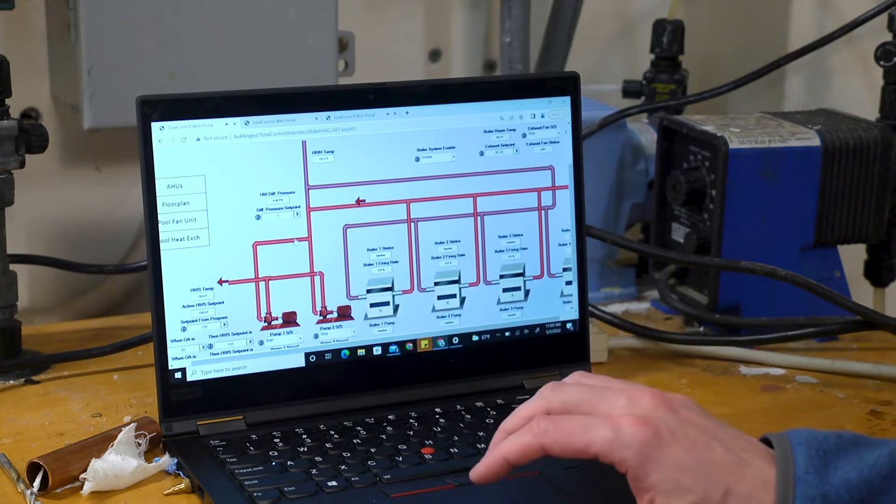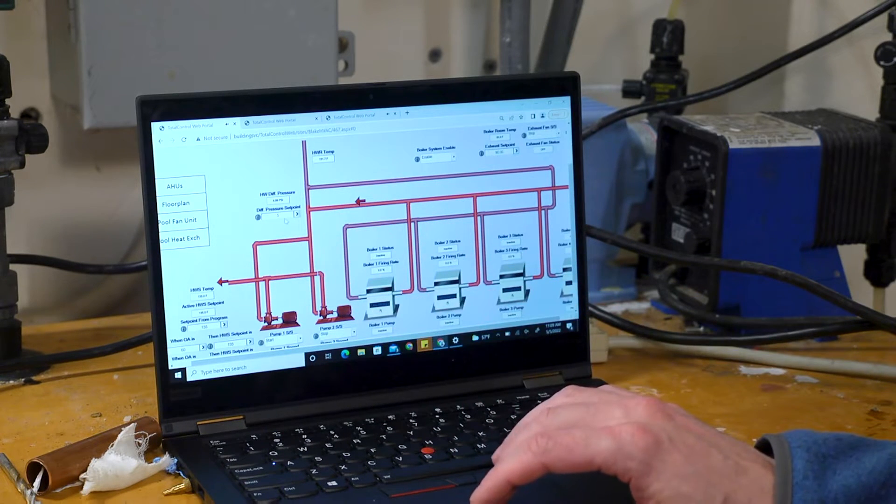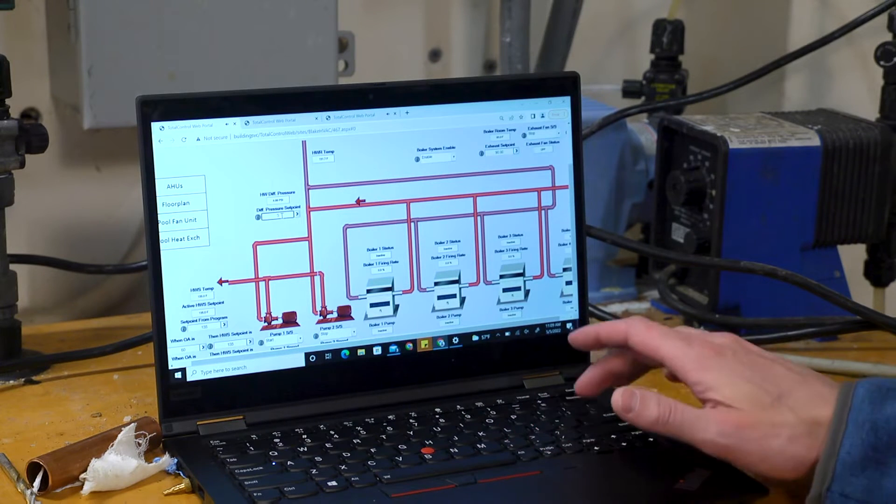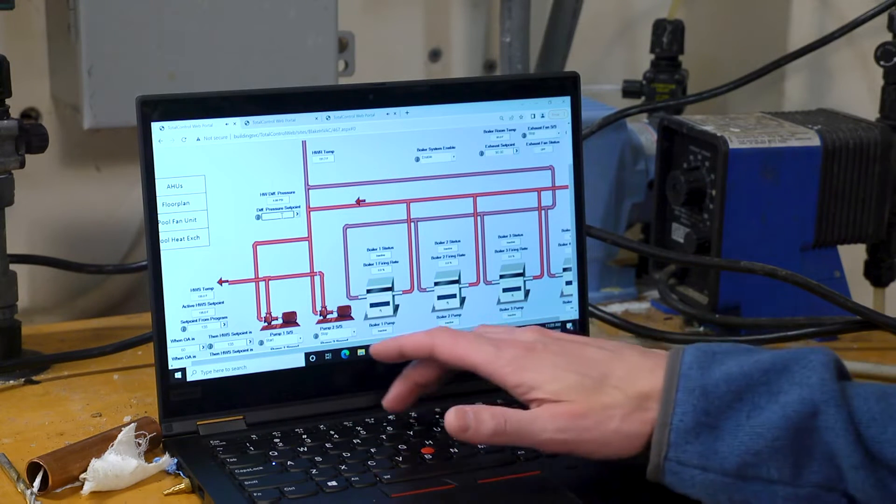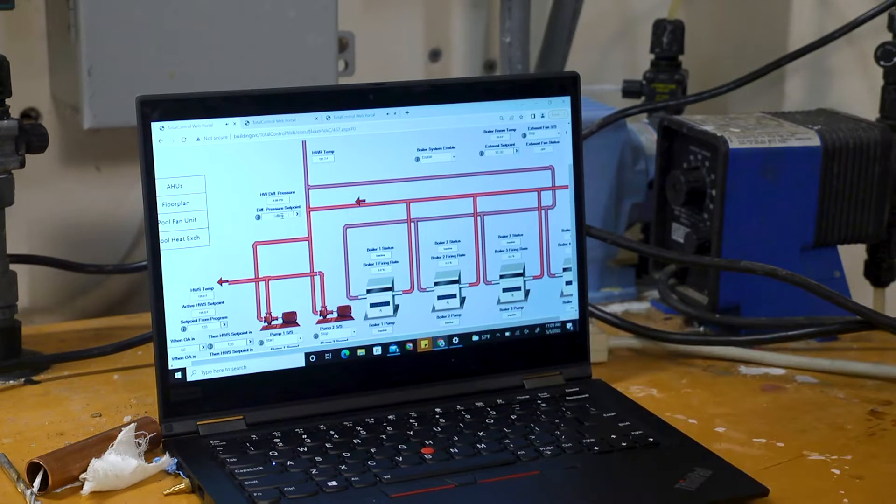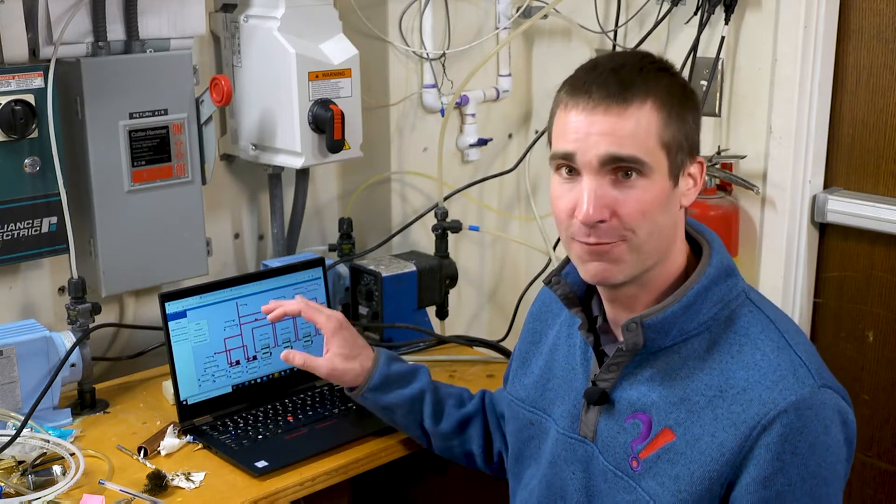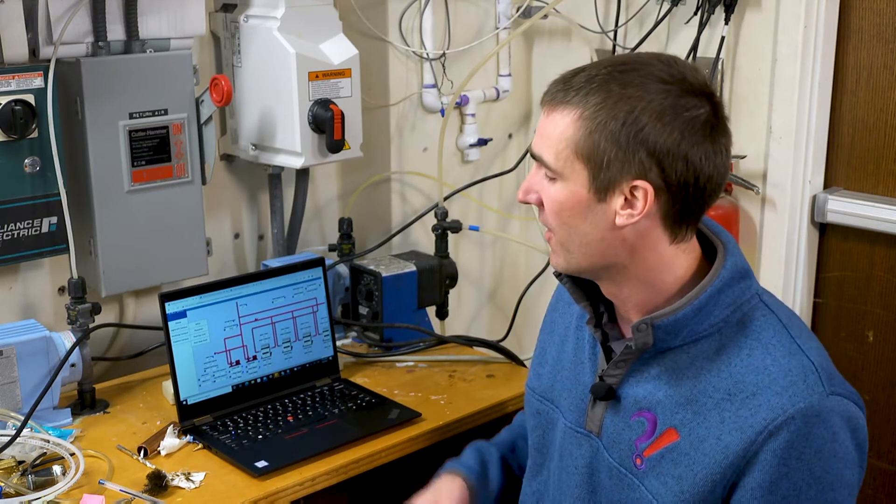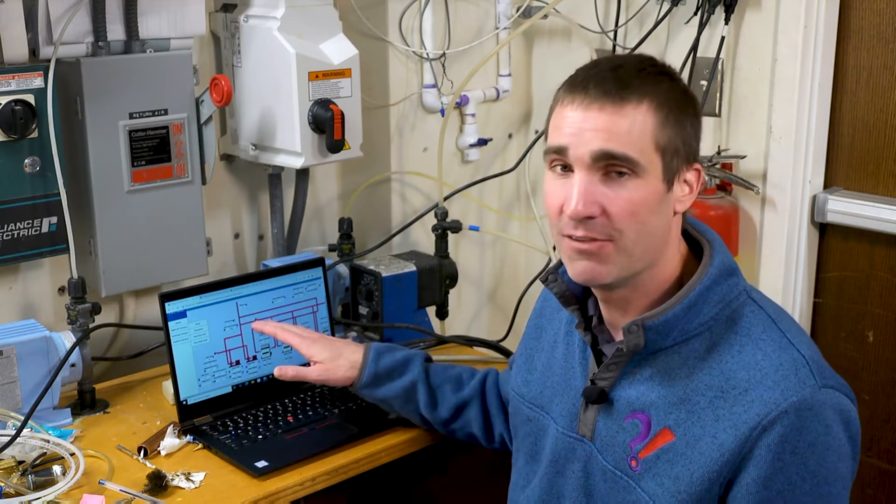If someone was to ever come in here and deviate from 5, this system has a cool feature which will set up a flag to say, hey, the default value of 5, which was determined during the construction phase by the testing, adjusting, and balancing contractor, someone's deviated from that value.